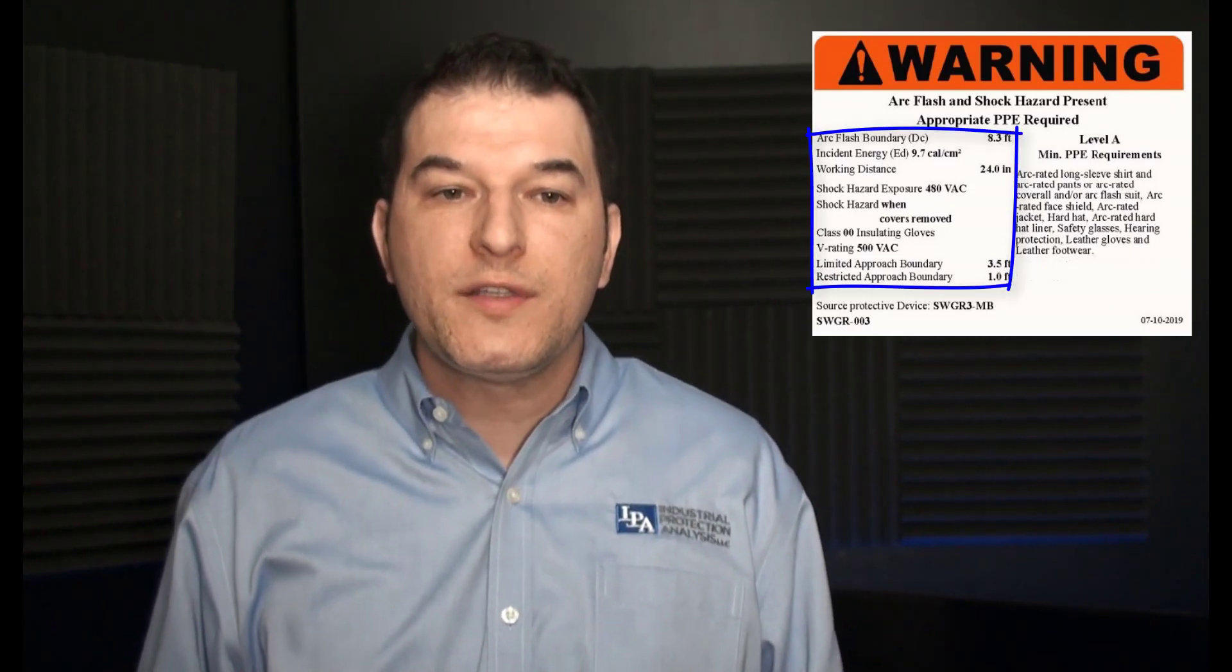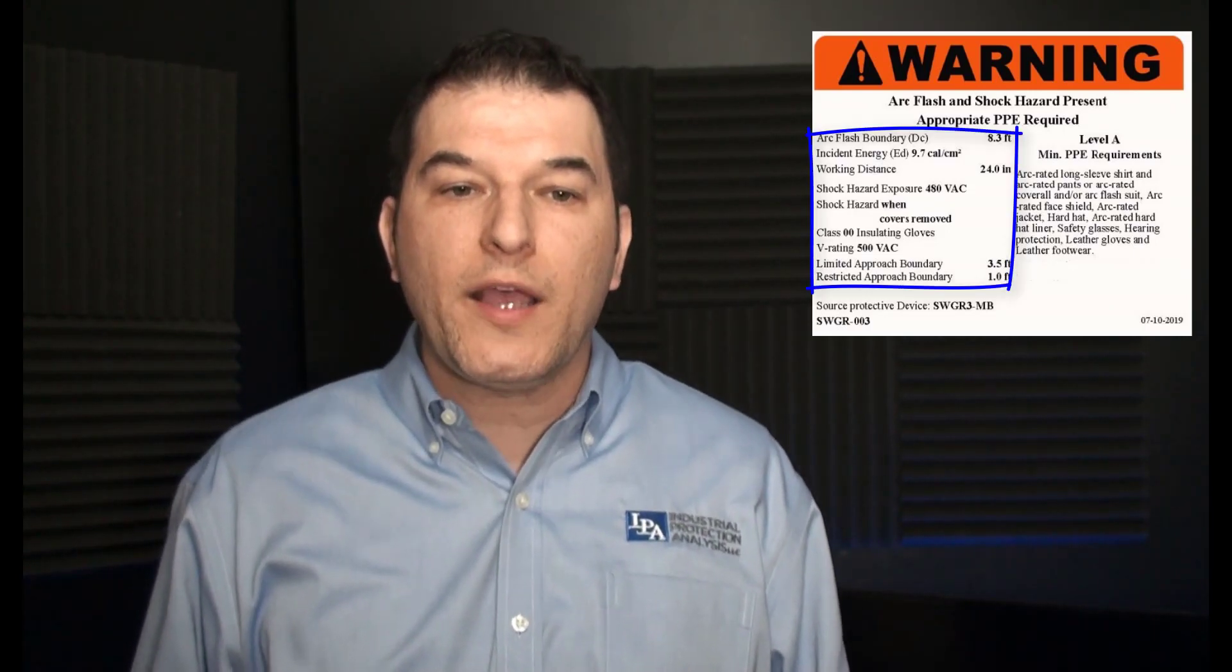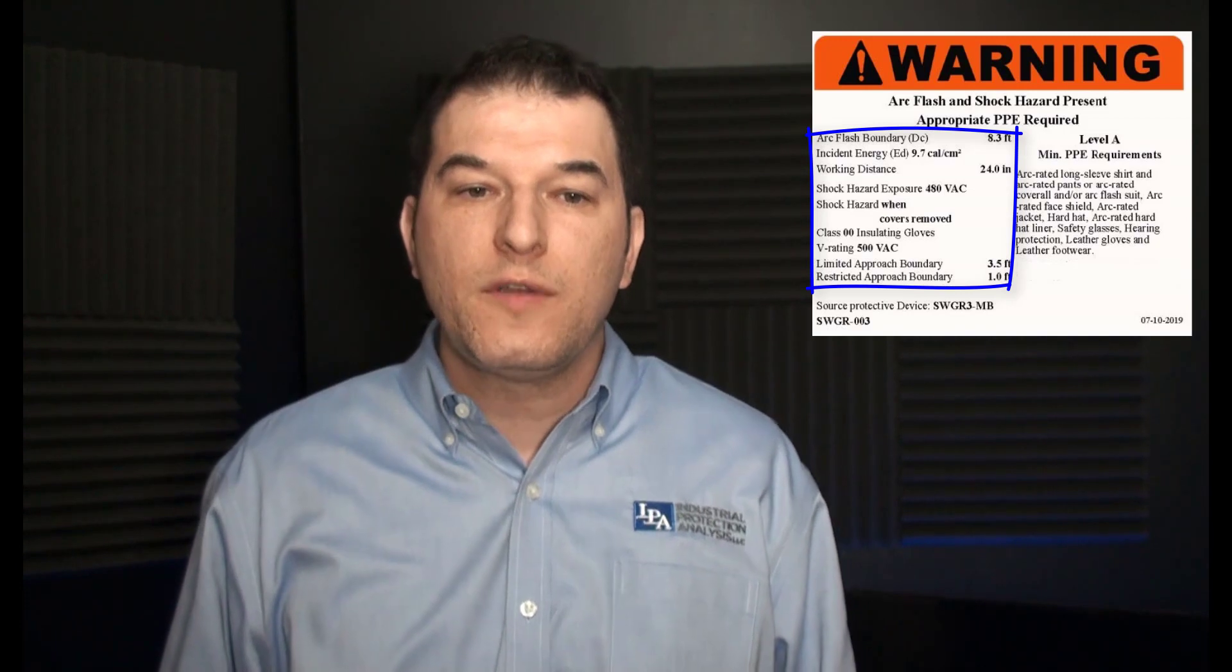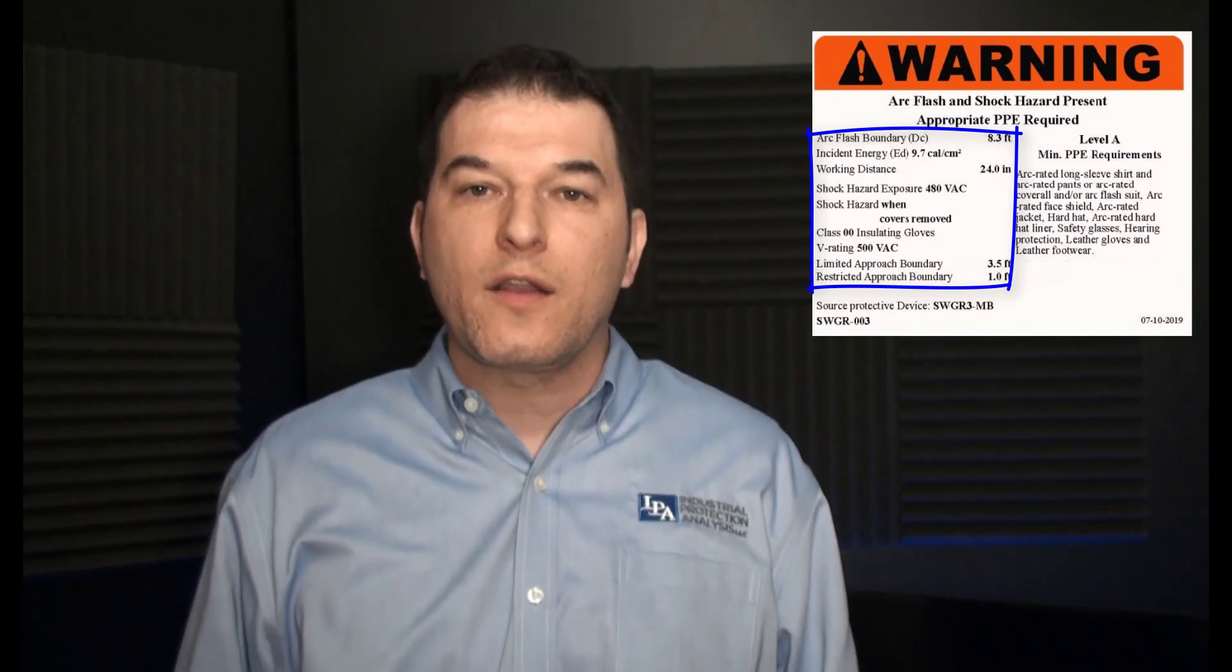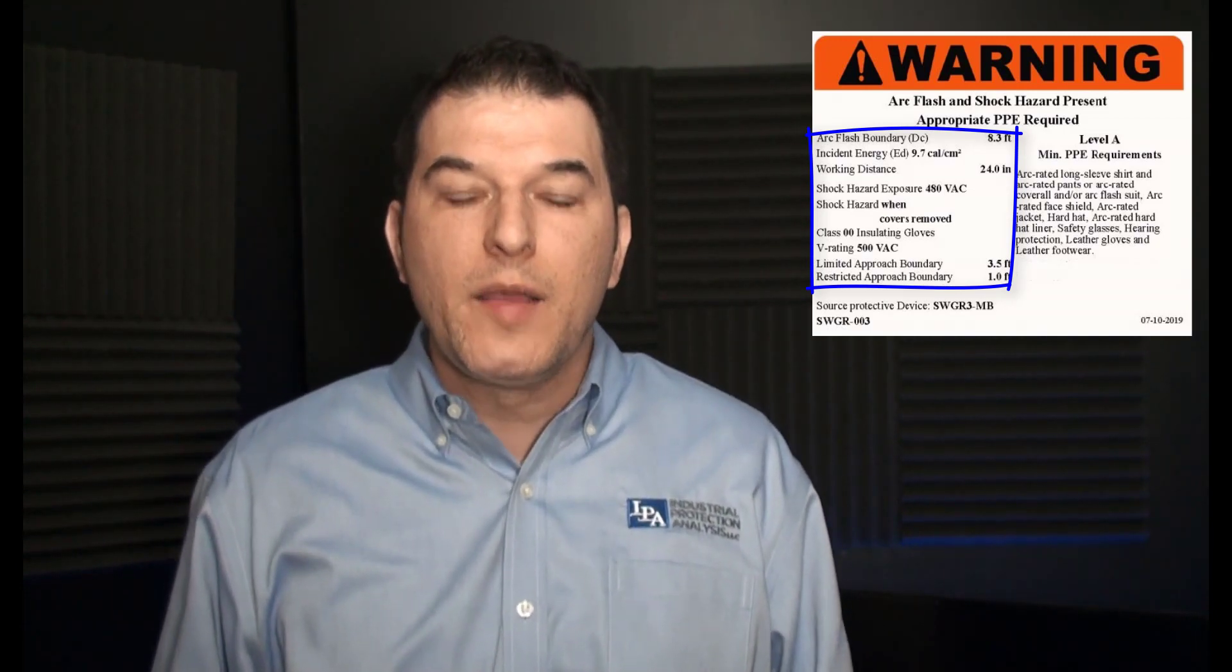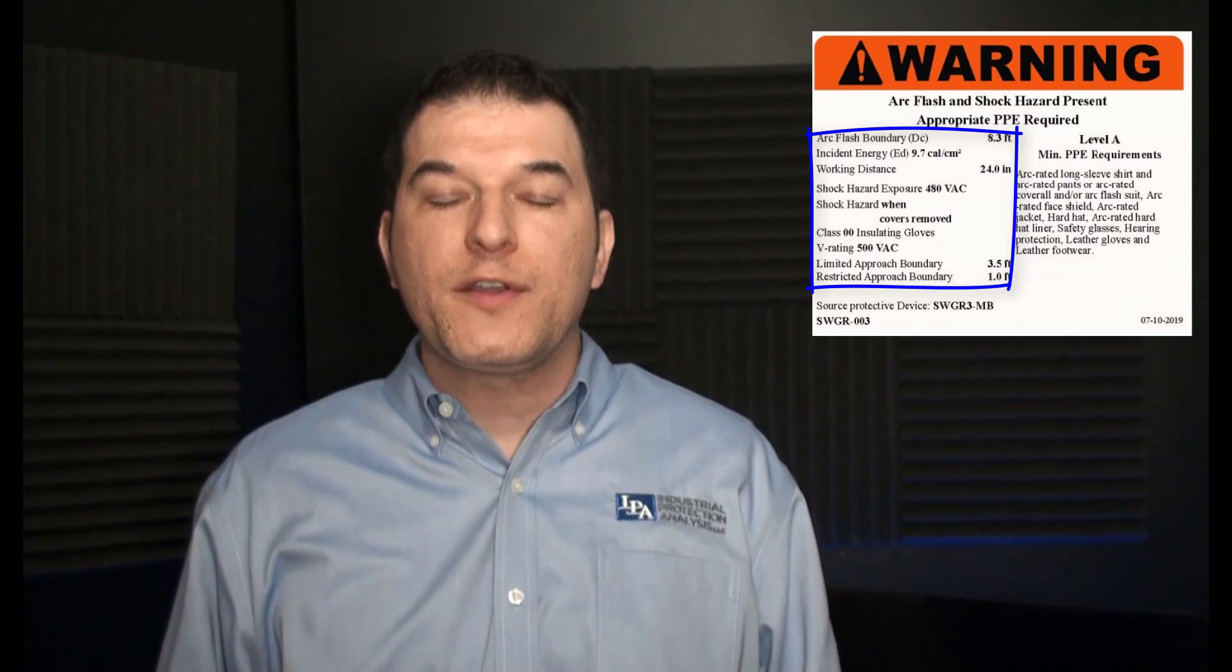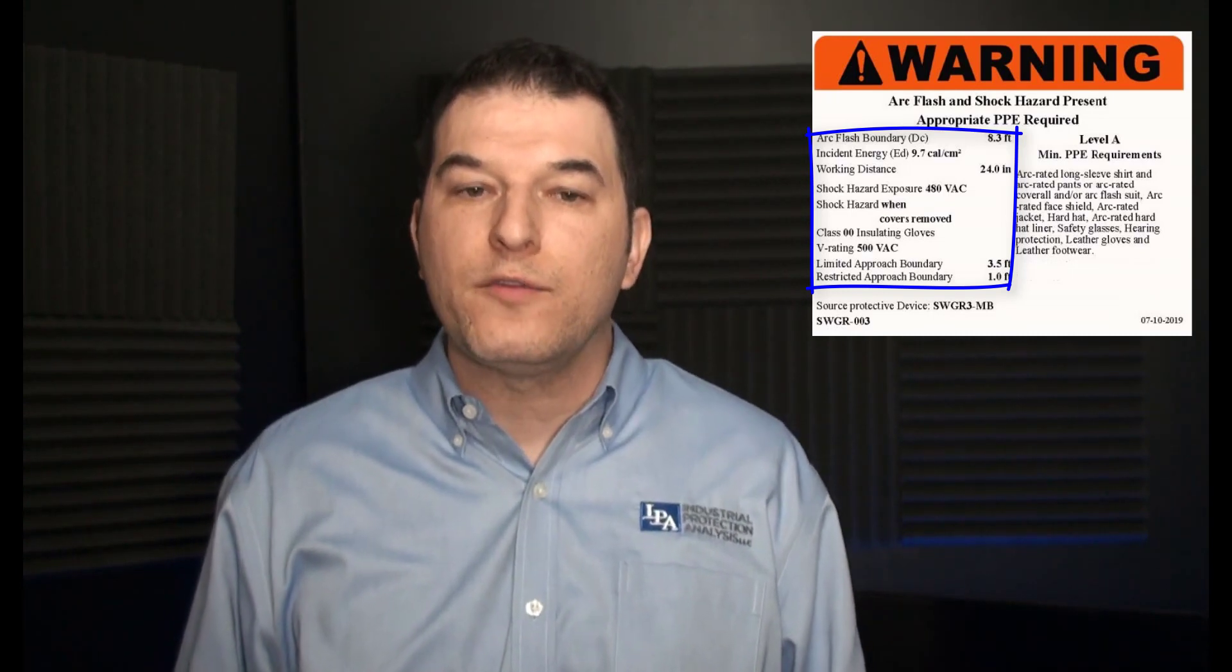Here is a sample Arc Flash label. It shows incident energy, working distance, shock hazard exposure, voltage, class of insulating gloves, limited approach boundary, restricted approach boundary. Here I want to make an observation. With the NFPA 70E revision 2015, the prohibited approach boundary has been removed from the standard.